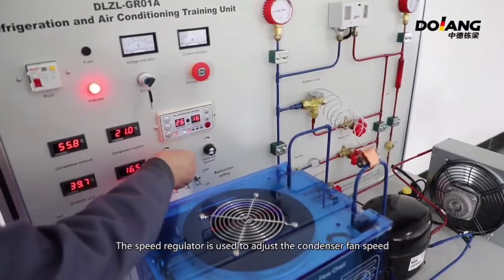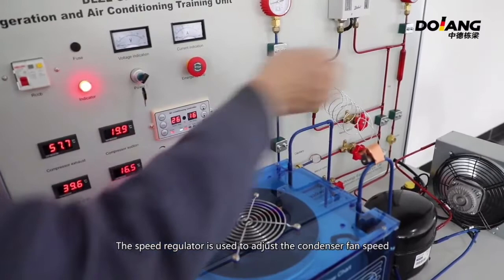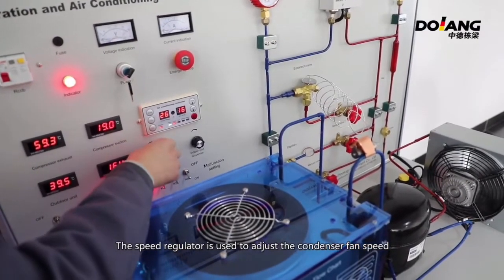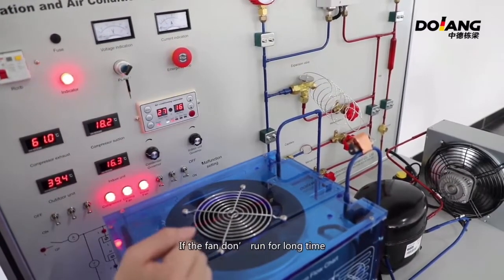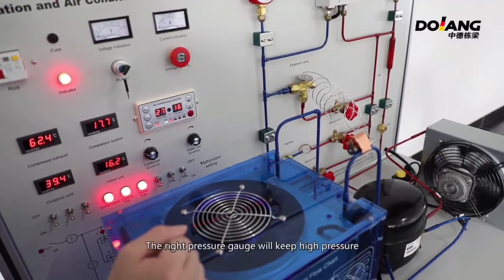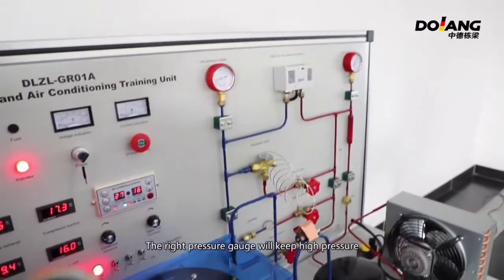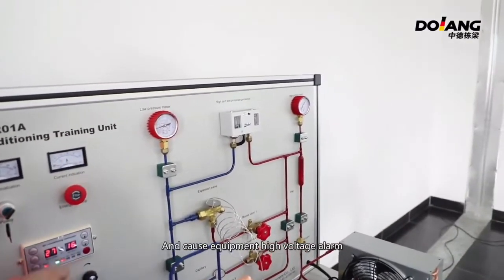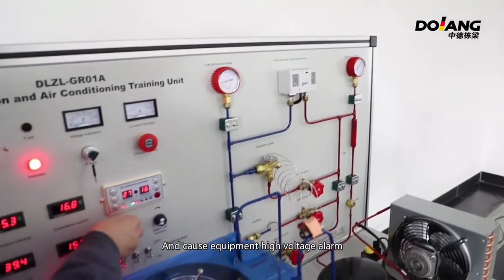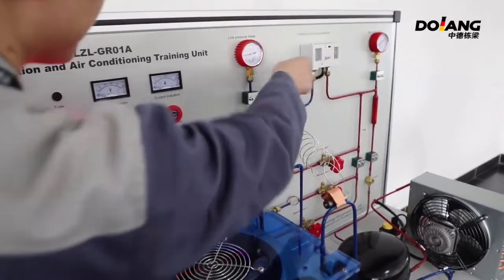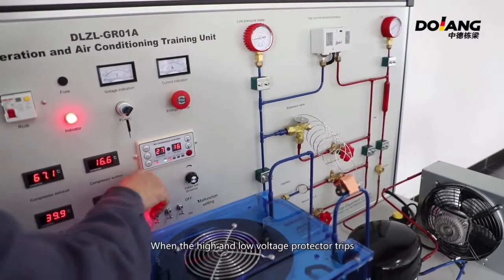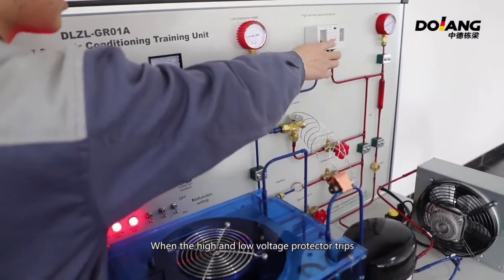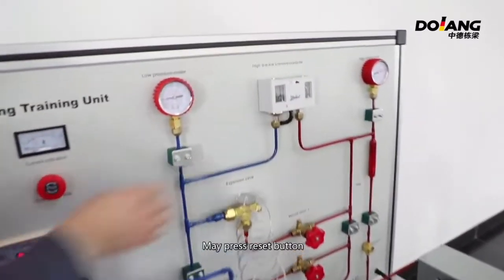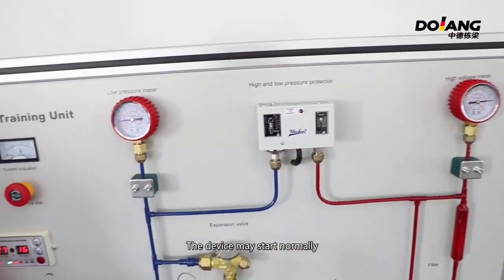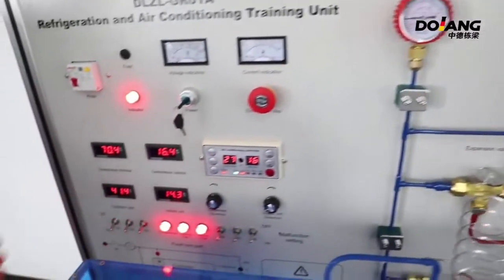The speed regulator is used to adjust the condenser fan speed. If the fan doesn't run for a long time, the right pressure gauge will keep high pressure and cause the equipment's high pressure alarm. When the high and low pressure protector trips, you may press the reset button. The device may start normally.